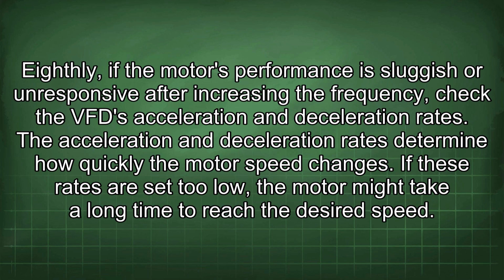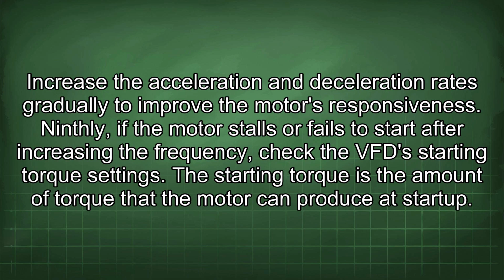Eighthly, if the motor's performance is sluggish or unresponsive after increasing the frequency, check the VFD acceleration and deceleration rates. The acceleration and deceleration rates determine how quickly the motor speed changes. If these rates are set too low, the motor might take a long time to reach the desired speed. Increase the acceleration and deceleration rates gradually to improve the motor's responsiveness.